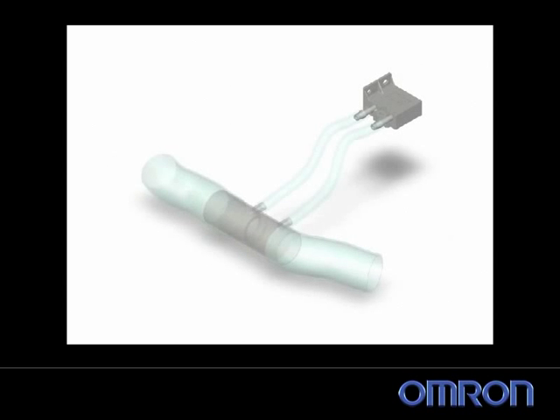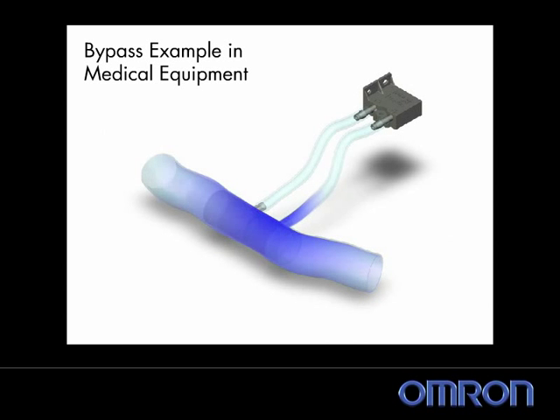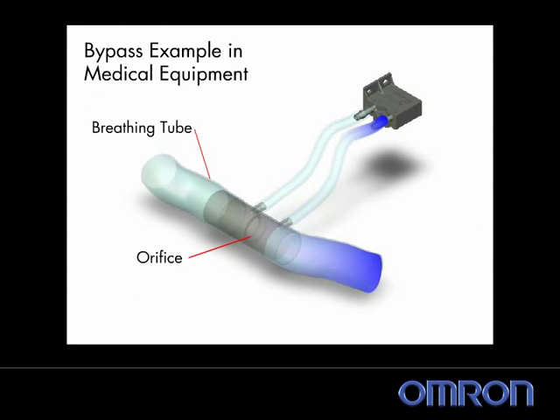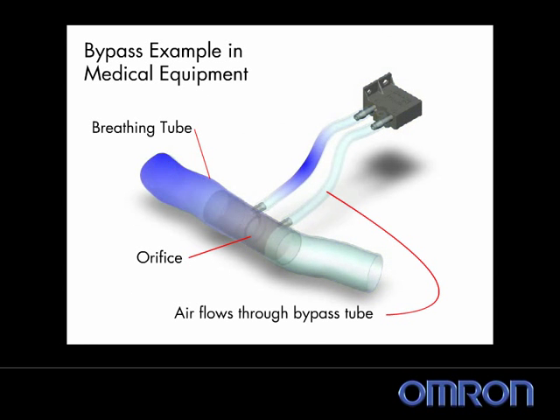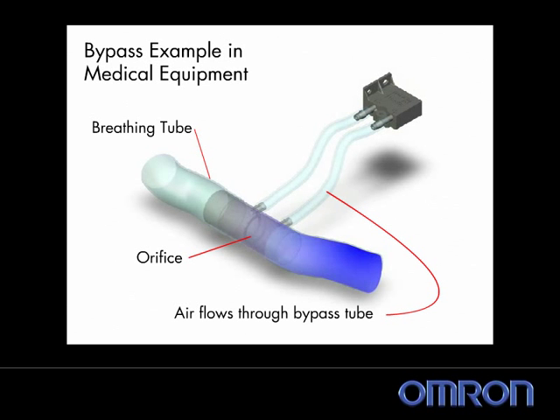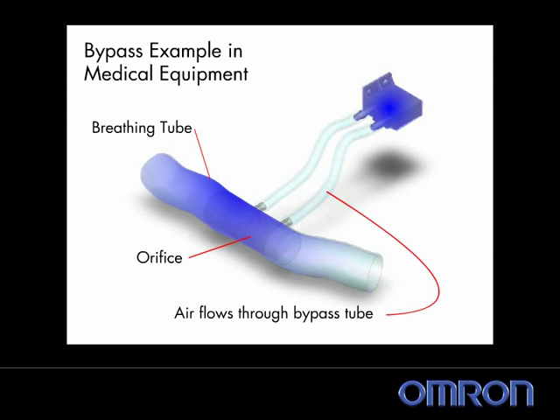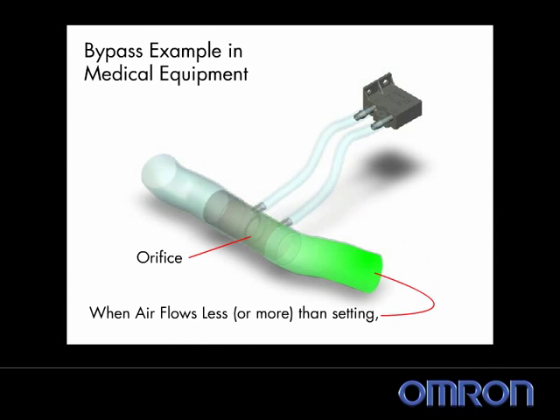This animation shows how a D6F-P might be used in a bypass setup for a medical application. The one LPM device can be used to measure a proportional amount of the flow going through the main tube, making it possible to use a smaller, less expensive device in applications requiring up to 200 LPM.